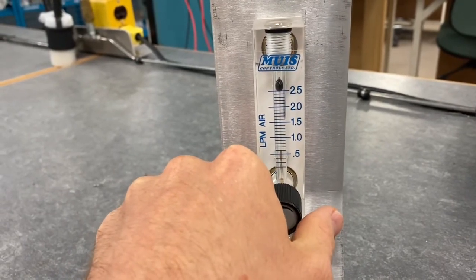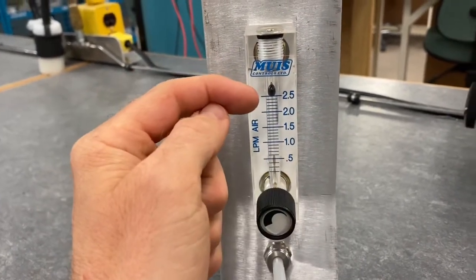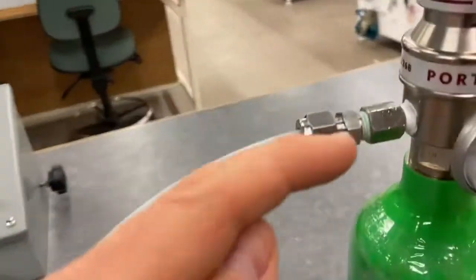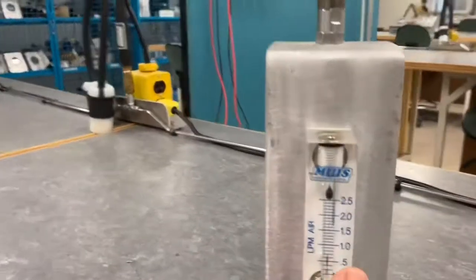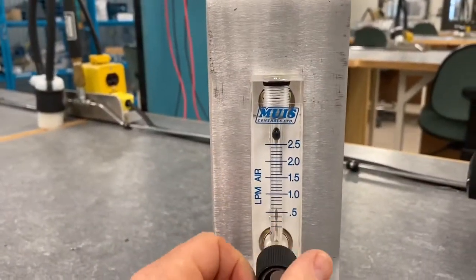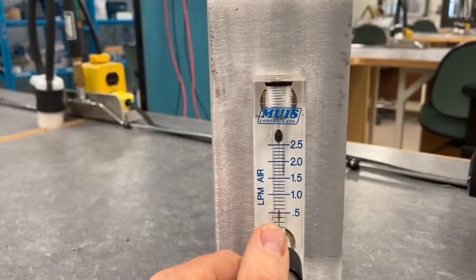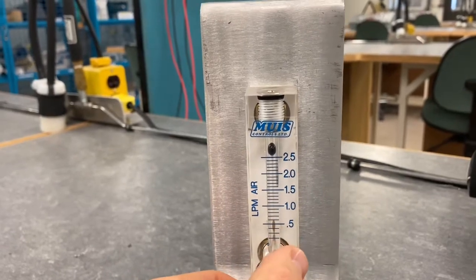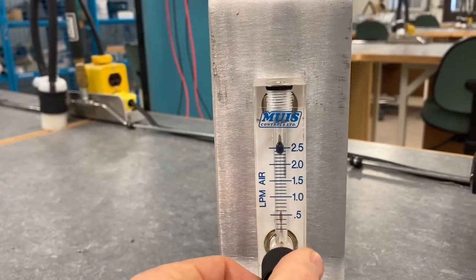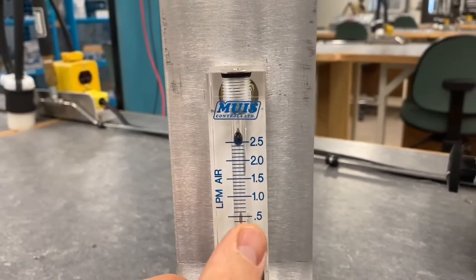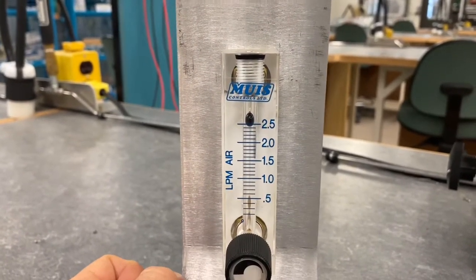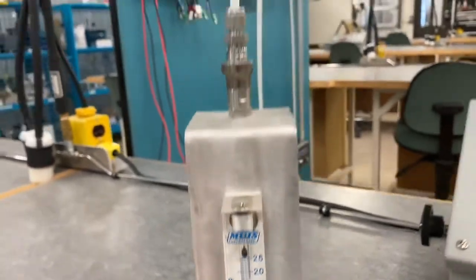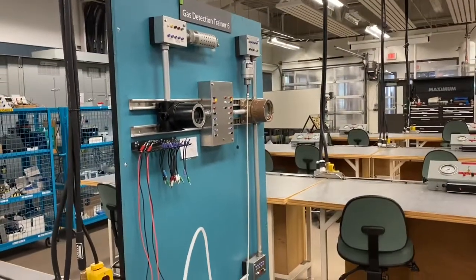You can see I can go close to that. This limiter is limiting us to about 2.5 liters per minute, and that shows right here. I can't get it to go much higher. The ball wants to fall back down. We would do the same thing here. We would set this to the correct flow rate, and I'm just putting it to the high end. There's a value you have to look up in your manuals. Now we would have that flowing out into our sensor when we need to do the calibration.